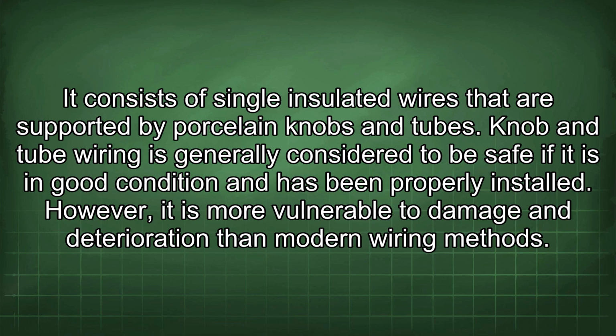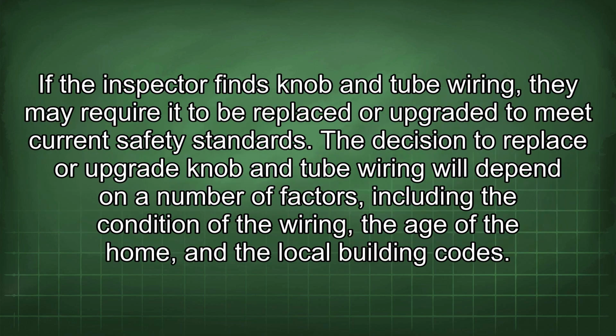Knob and tube wiring is generally considered to be safe if it is in good condition and has been properly installed. However, it is more vulnerable to damage and deterioration than modern wiring methods. If the inspector finds knob and tube wiring, they may require it to be replaced or upgraded to meet current safety standards. The decision to replace or upgrade knob and tube wiring will depend on a number of factors, including the condition of the wiring, the age of the home, and the local building codes.